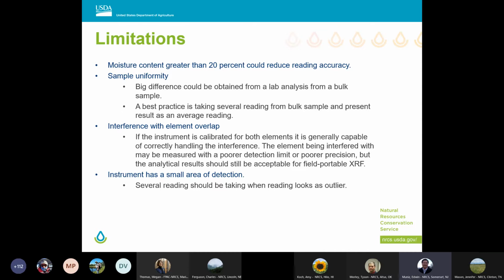So if you have a big sample or bulk sample that you send to the lab, you might get a huge difference between your readings, because the capture area for the instrument is very small. So one of the best practices for bulk samples is taking several readings and then presenting results as average readings. Those will probably be a lot closer to the data that comes from the lab for bulk samples.